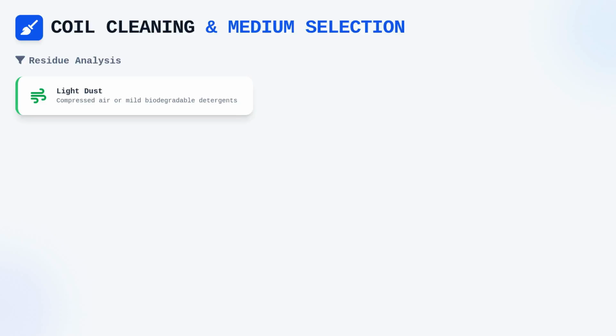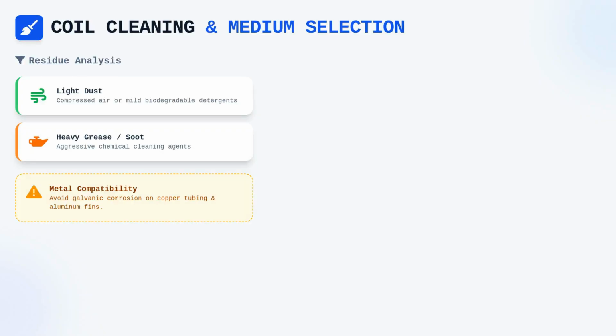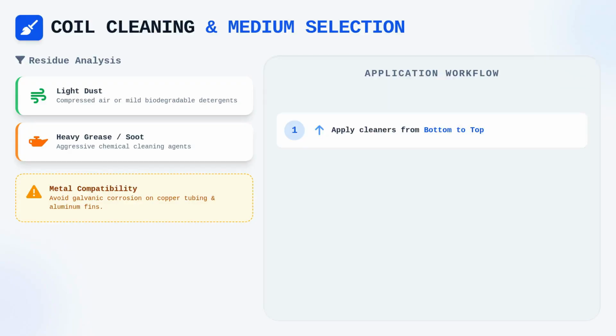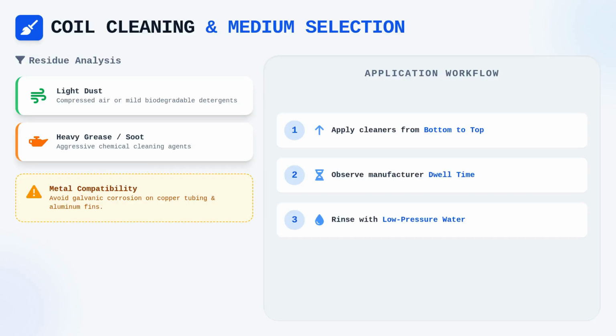Selecting the appropriate cleaning medium requires an understanding of the residue encountered. For light dust, compressed air or mild biodegradable detergents are usually sufficient, but heavy grease or baked-on industrial soot demands more aggressive chemical agents. When applying chemical cleaners, you must ensure compatibility with the coil metal, which is typically copper tubing with aluminum fins, to avoid galvanic corrosion or the pitting of base metals. Always apply cleaners from the bottom up to ensure uniform coverage and allow for appropriate dwell time as specified by the manufacturer before rinsing thoroughly with low-pressure water.